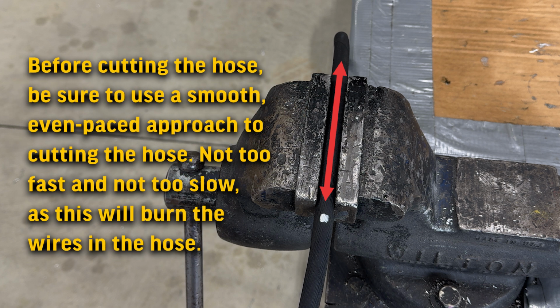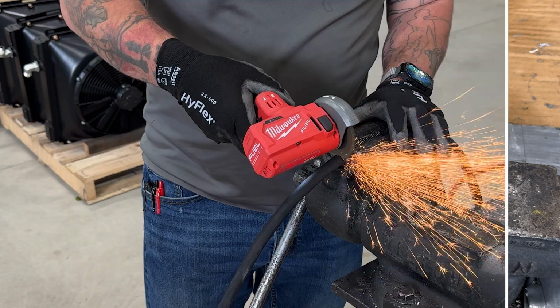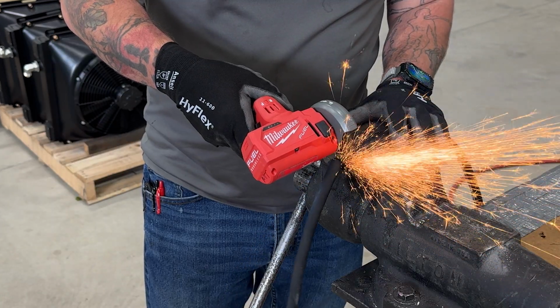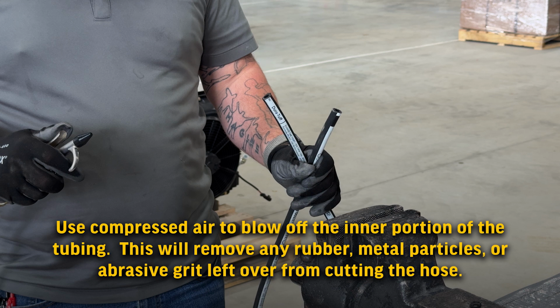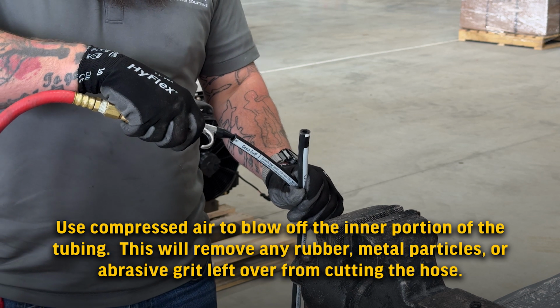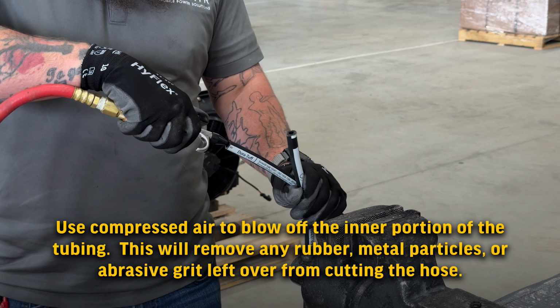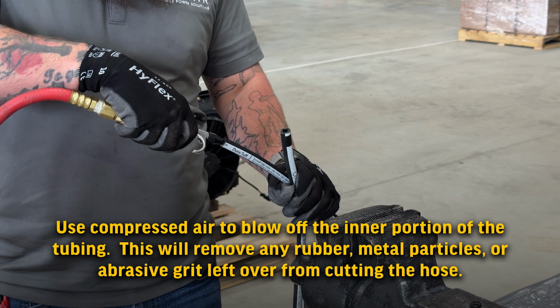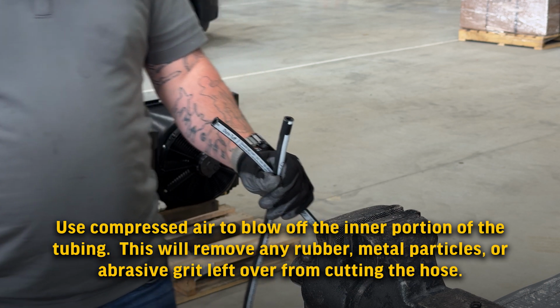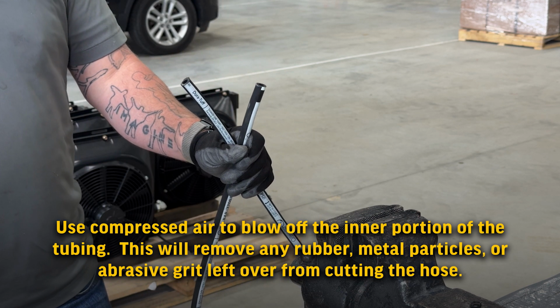Before cutting the hose, be sure to use a smooth, even paced approach to cutting the hose. Not too fast and not too slow, as this will burn the wires in the hose. Cut the hose at the desired mark. Remove the hose from the vise and using compressed air, blow off the inner portion of the tubing. This will remove any rubber, metal particles, or abrasive grit left over from cutting the hose.